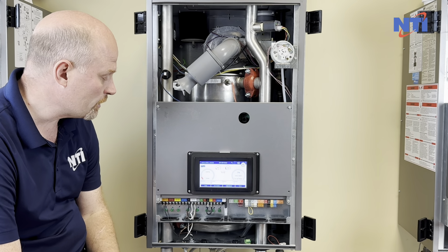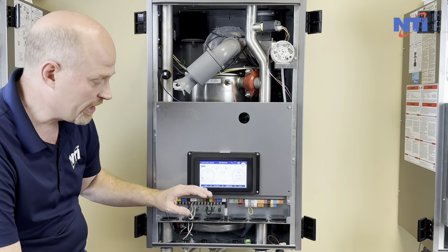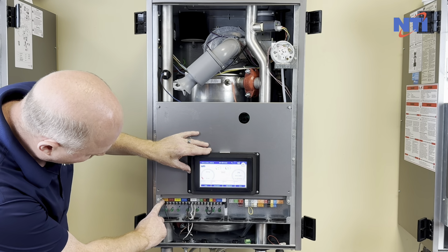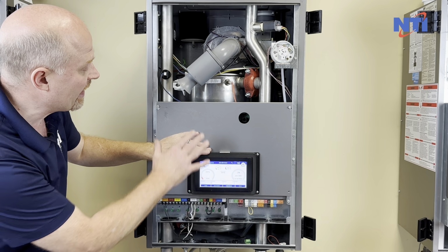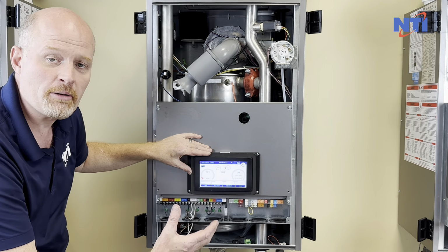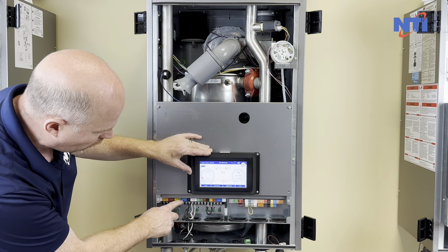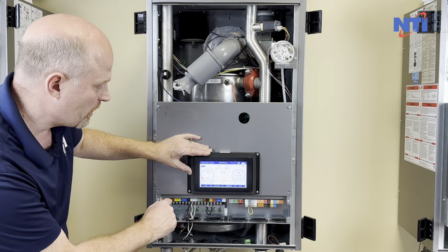Now, we get a lot of questions on pump controls, so that's what we're going to concentrate on today. On the boiler, you have a boiler pump. This pump runs for heating or hot water calls, or really anything that activates the boiler. You've got a DHW pump. That pump is only going to run when there's a domestic hot water call. There are two auxiliary pumps, and these have selectable functions, and that's what I'm going to show you next.